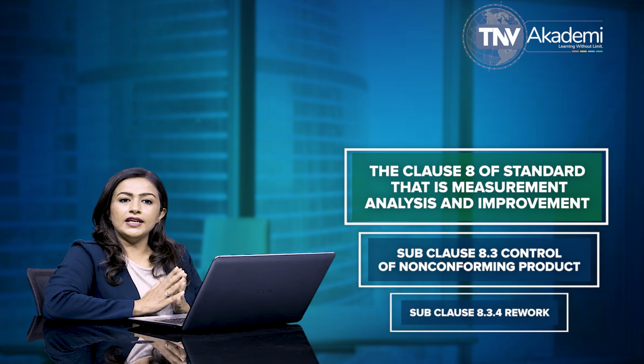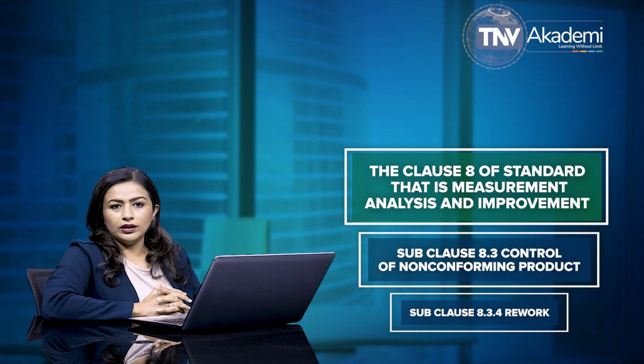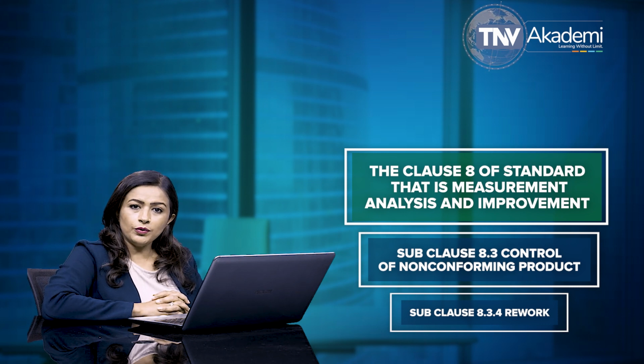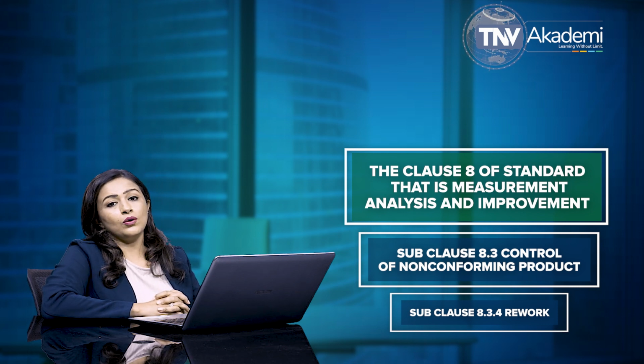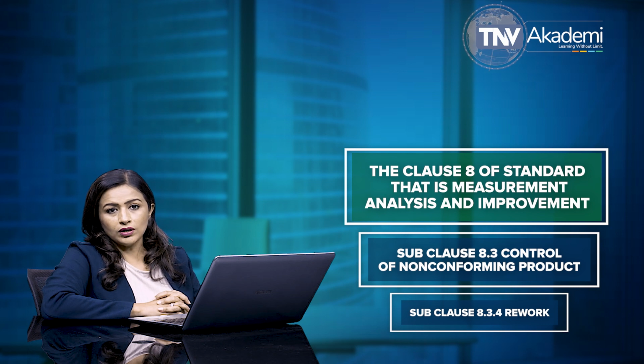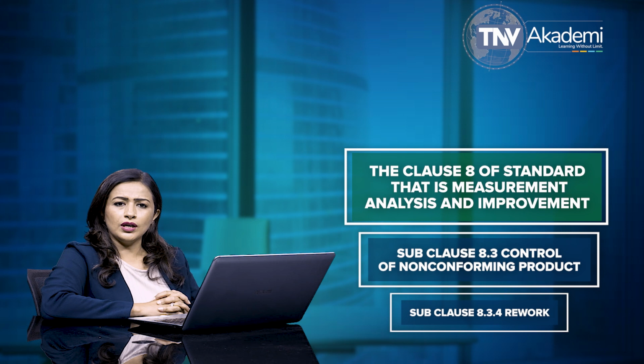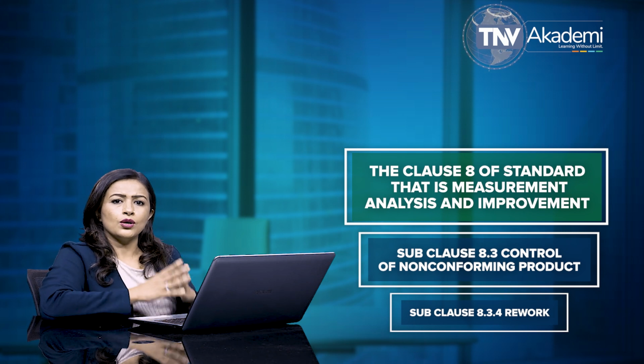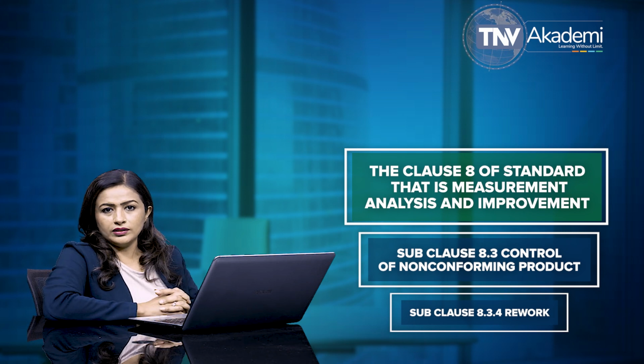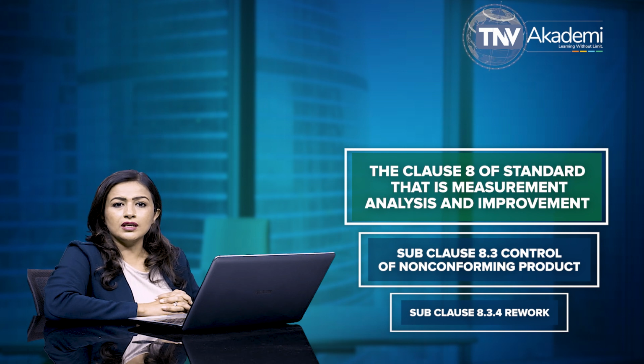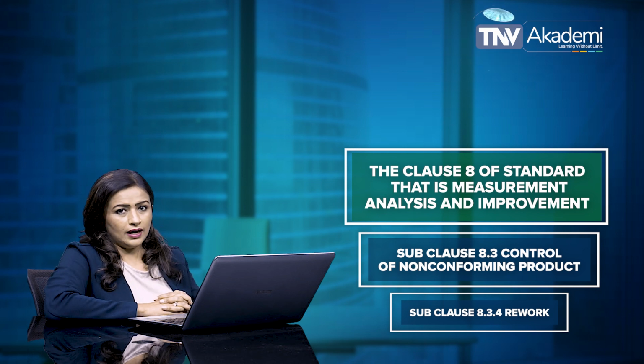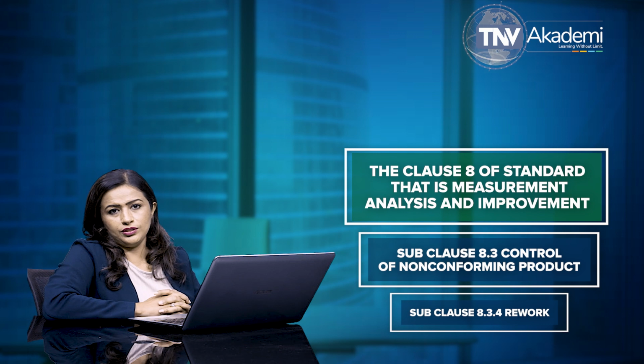Coming to subclause 8.3.4, rework. This subclause 8.3.4 states that the organization must perform rework in accordance with documented procedures that take into account the potential adverse effects of the rework on the product. These procedures must undergo the same review and approval as the original procedure.